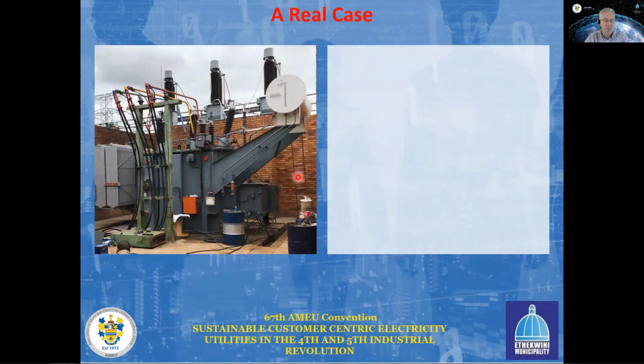I'd like to share a real case with you. In this picture here, you see a very typical 22 MVA transformer. In this case, it was 132 kV to 11 kV. It is situated at one of the major municipalities in this country. This transformer tripped, and it then was tested, and there was still some specific testing that needed to be done on this transformer before the municipality wanted to return it to service. The municipality couldn't do that test themselves, and as a result, this transformer stood idling, meaning it wasn't supplied and couldn't supply customers for many days, resulting in a huge problem for the customers, because the suburb that this transformer supplies didn't have electricity for at least 3 days.